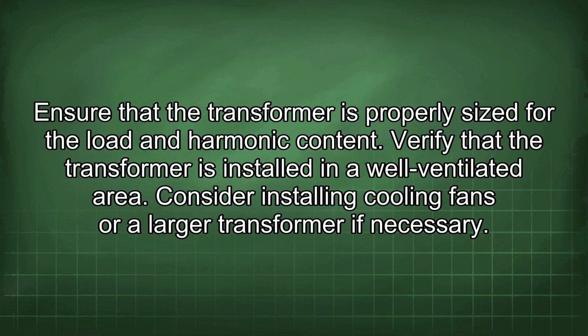Overheating can be caused by excessive harmonic currents, overloading, poor ventilation, or a combination of these factors. Ensure that the transformer is properly sized for the load and harmonic content. Verify that the transformer is installed in a well-ventilated area. Consider installing cooling fans or a larger transformer if necessary.